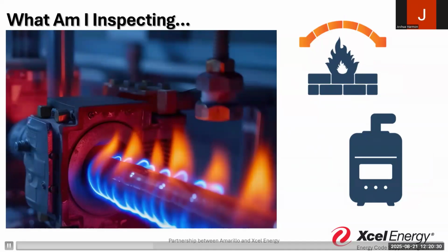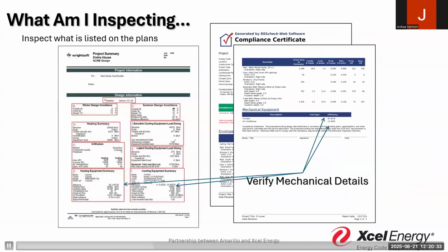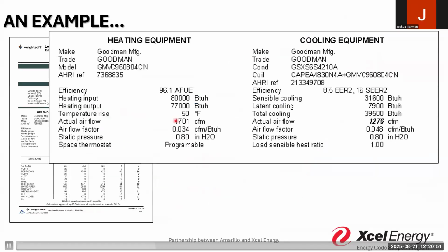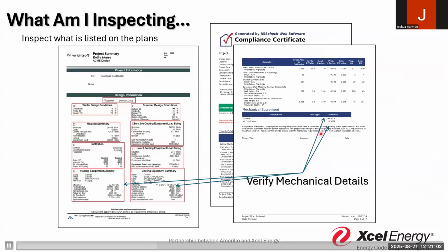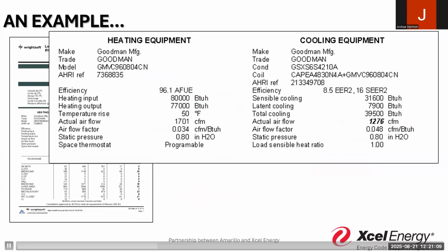Because what I'm inspecting and what I'm expecting is what's on the plans. So if I've got a Manual J and a REScheck that says we're supposed to have an air conditioner that's 15 SEER and a furnace that's 92 AFUE, 92% efficient, and I show up to find it's 96%, okay, that's more efficient, but I've got an 8.5 EER2, or a 16 SEER2. How does a 16 SEER2 correlate to a 15 SEER? I'm not doing the math on this. Someone's going to have to verify for me as an inspector that this is the right piece of equipment, because I'm expecting equipment that provides an output of 77,000 BTU and is 96% efficient.